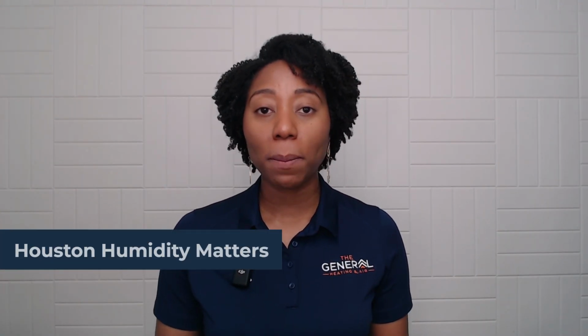Because we live in Houston, humidity deserves its own conversation. One of the biggest reasons homeowners move beyond single-stage equipment isn't usually temperature, it's moisture. You've probably been in a home where the thermostat says 72 degrees but it still feels sticky and muggy. That's because comfort isn't just about temperature. Air conditioners also remove moisture from the air, and the longer they run, the more opportunities they have to do that. A single-stage system tends to run shorter cycles. Two-stage runs a little longer, but variable speed runs very long, which is why Houston area homeowners may notice meaningful differences in humidity control between these categories.